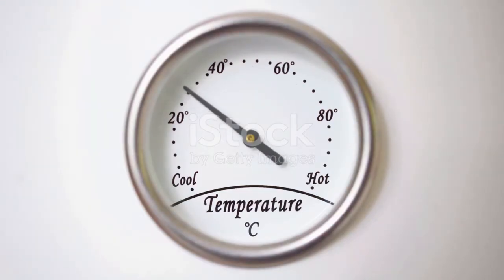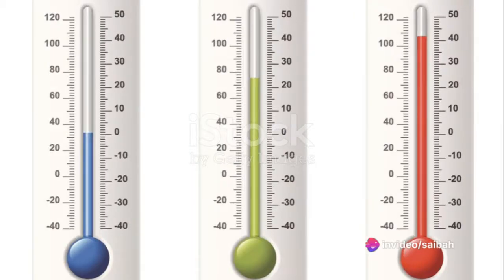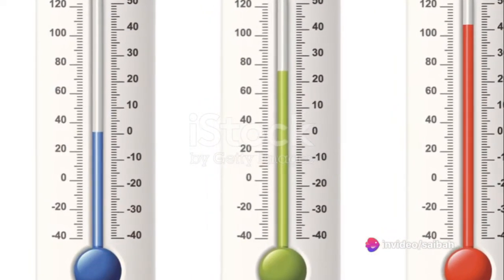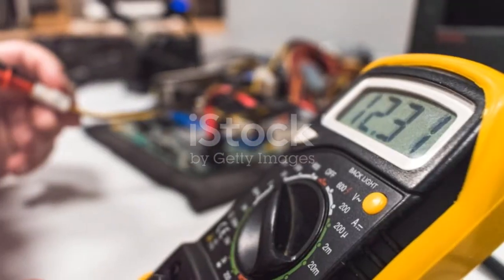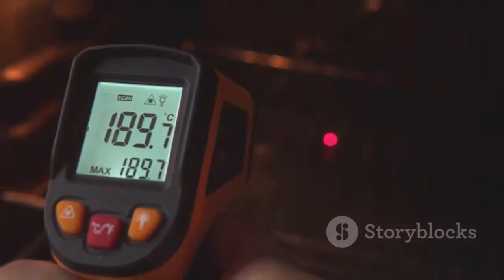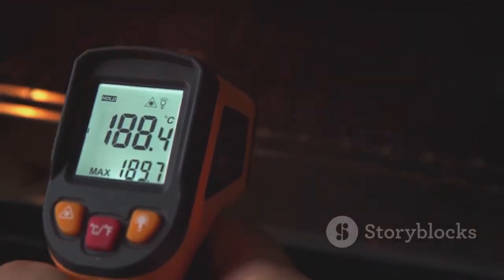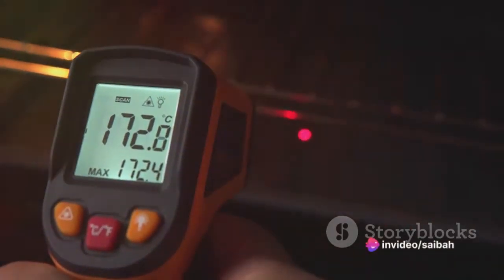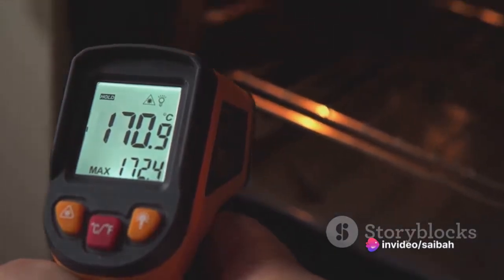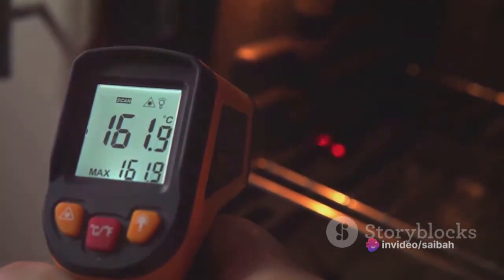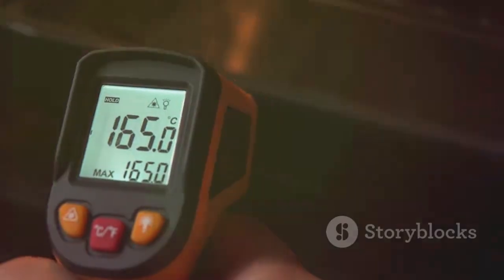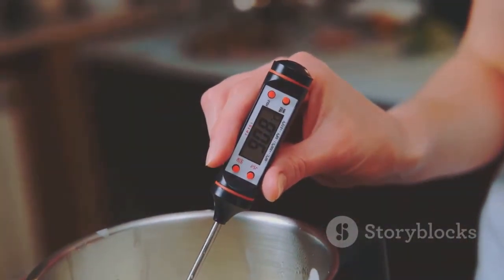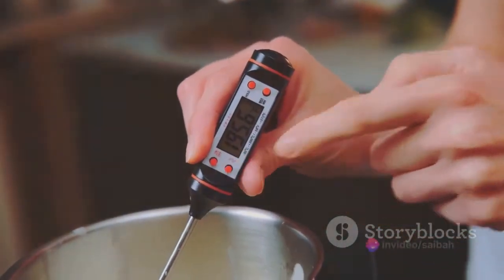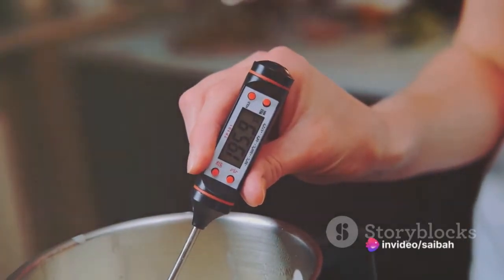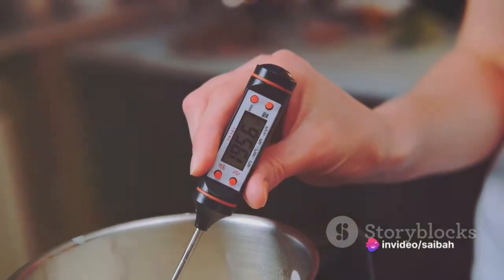Next, you'll need a reliable heat source. This could be anything from a controlled heat bath to a simple space heater, as long as it can steadily increase and maintain the desired temperature. Lastly, you're going to need a multimeter. This tool will allow you to measure the electrical resistance of the temperature switch, helping you determine whether it's operating within the acceptable range. Remember, it's not just about having these tools at your disposal. It's also crucial that they are calibrated correctly. Accurate results hinge on the precision of your tools. With the right tools in hand, you're set to begin the calibration process.